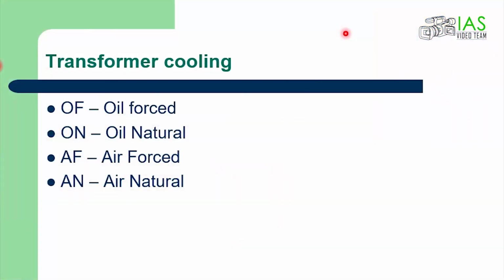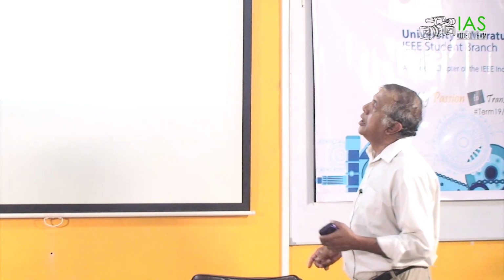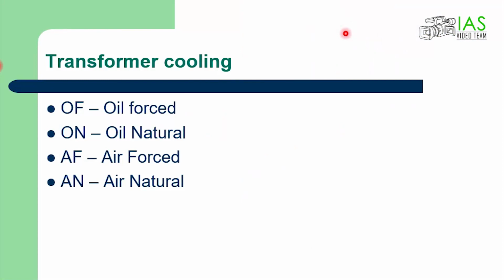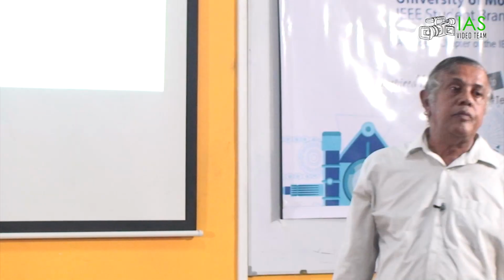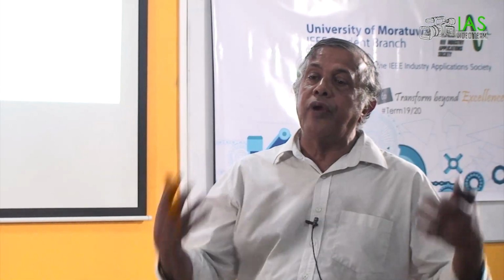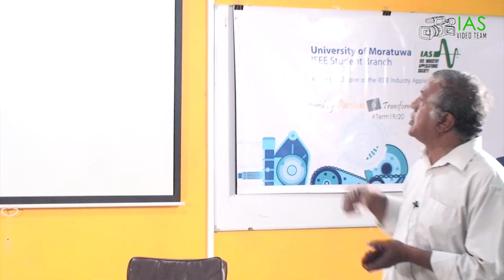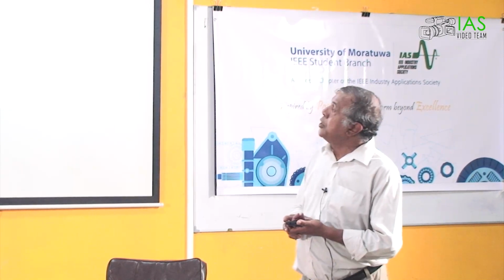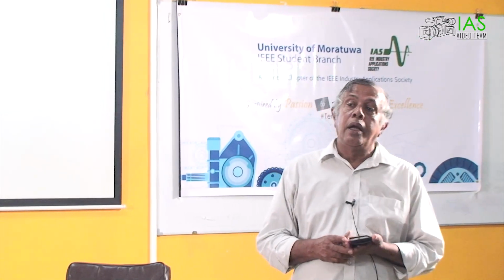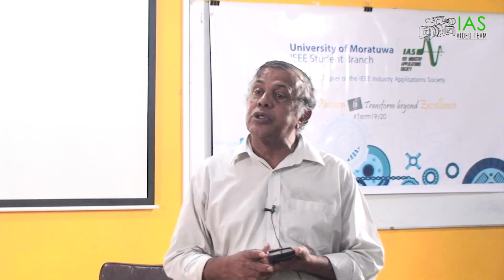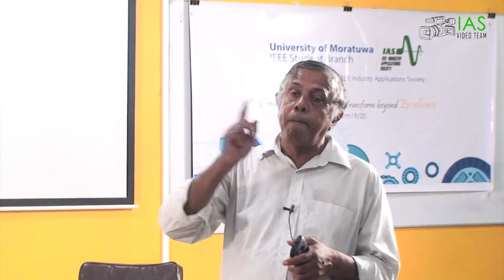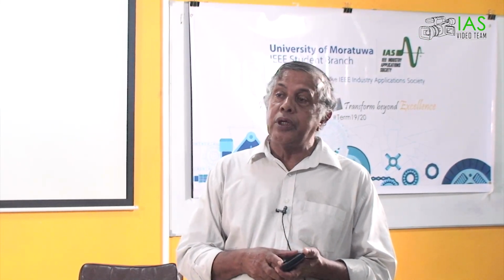So, transformer cooling. Now, we talked about the pumps to push oil. OF is oil forced and ON is oil natural. AF is air forced and AN is air natural. Air forced is radiator and fans, right? If you don't have fans, then it's AN, air natural. So oil natural is ON and OF is oil forced. Only on oil forced transformers do you have forced circulation.